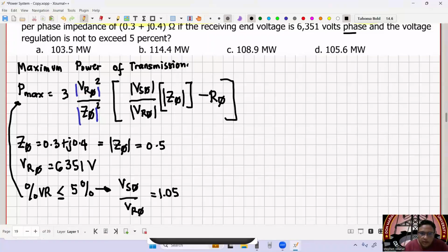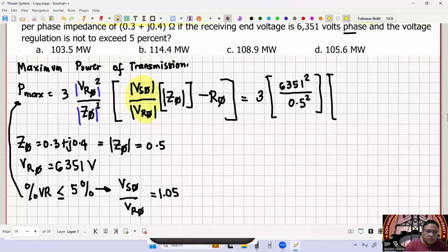Sige, apply natin dito. So this is now equal to 3 multiplied by VR per phase, that is 6,351, all over Z per phase, that is 0.5, and lahat ng to naka-squared. Multiplied by the quantity VS per phase over VR per phase - ito yon, this is only just the percent voltage regulation, so this is 1.05 - multiplied by Z per phase in magnitude, that is times 0.5, minus R per phase, that is 0.3. So therefore, what's now your Pmax?